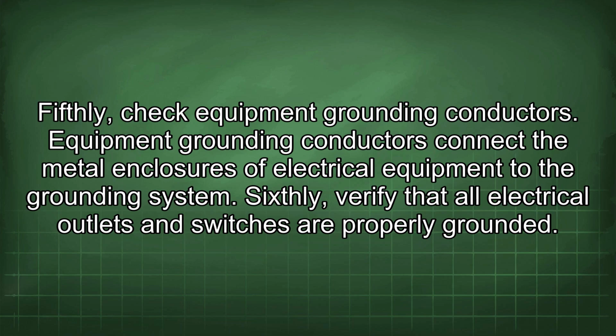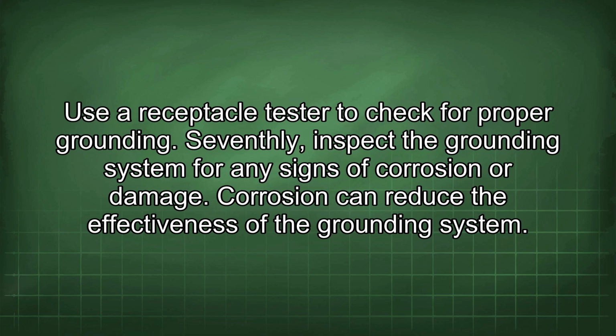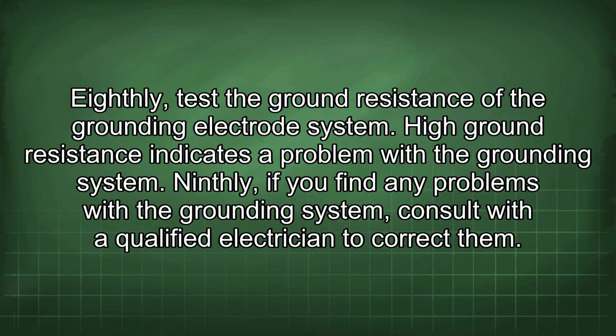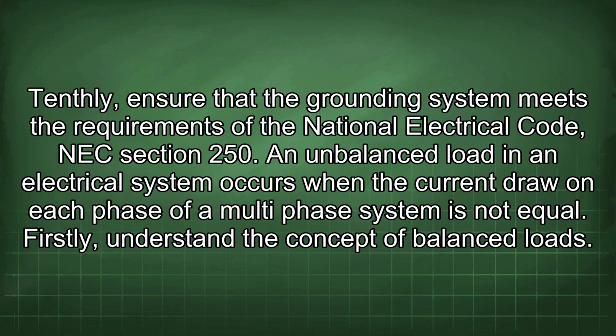Sixthly, verify that all electrical outlets and switches are properly grounded. Use a receptacle tester to check for proper grounding. Seventhly, inspect the grounding system for any signs of corrosion or damage. Corrosion can reduce the effectiveness of the grounding system. Eighthly, test the ground resistance of the grounding electrode system. High ground resistance indicates a problem with the grounding system. Ninthly, if you find any problems with the grounding system, consult with a qualified electrician to correct them. Tenthly, ensure that the grounding system meets the requirements of the National Electrical Code, NEC Section 250.